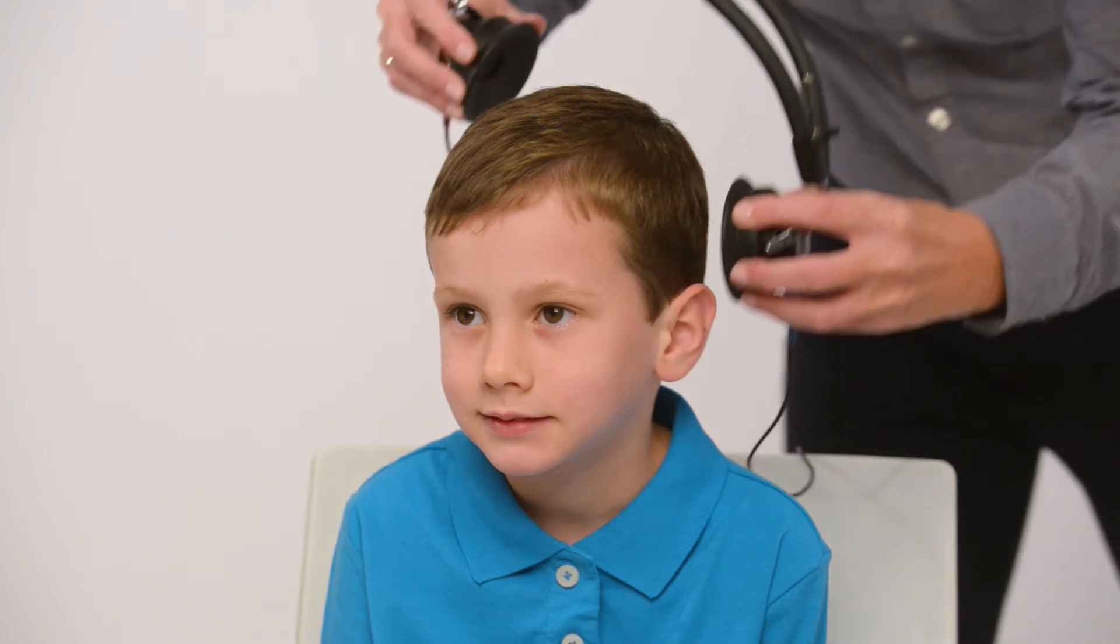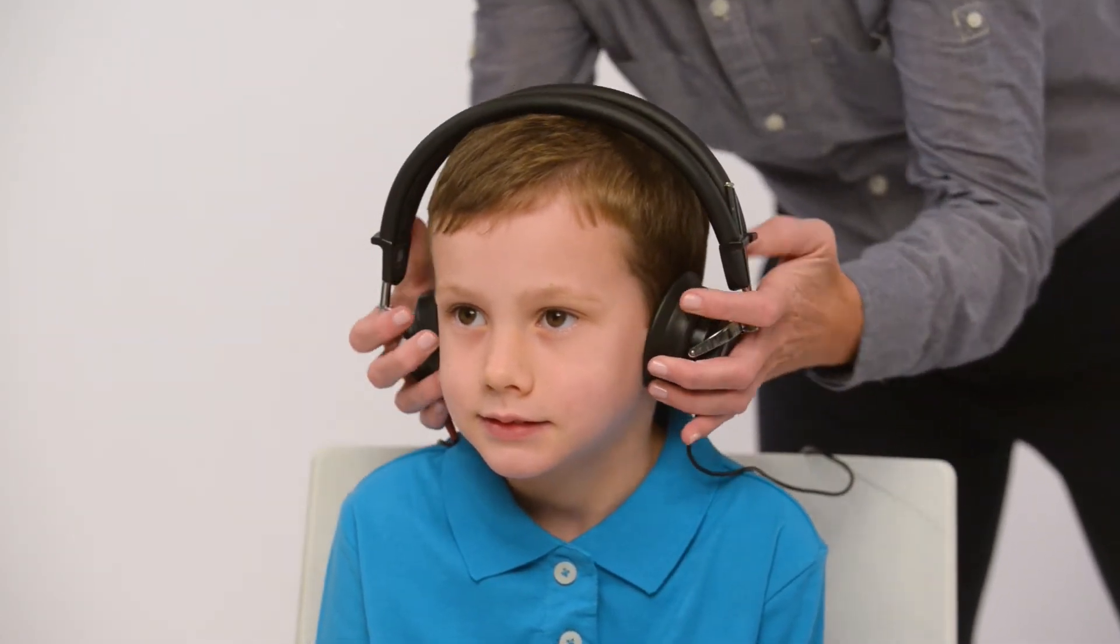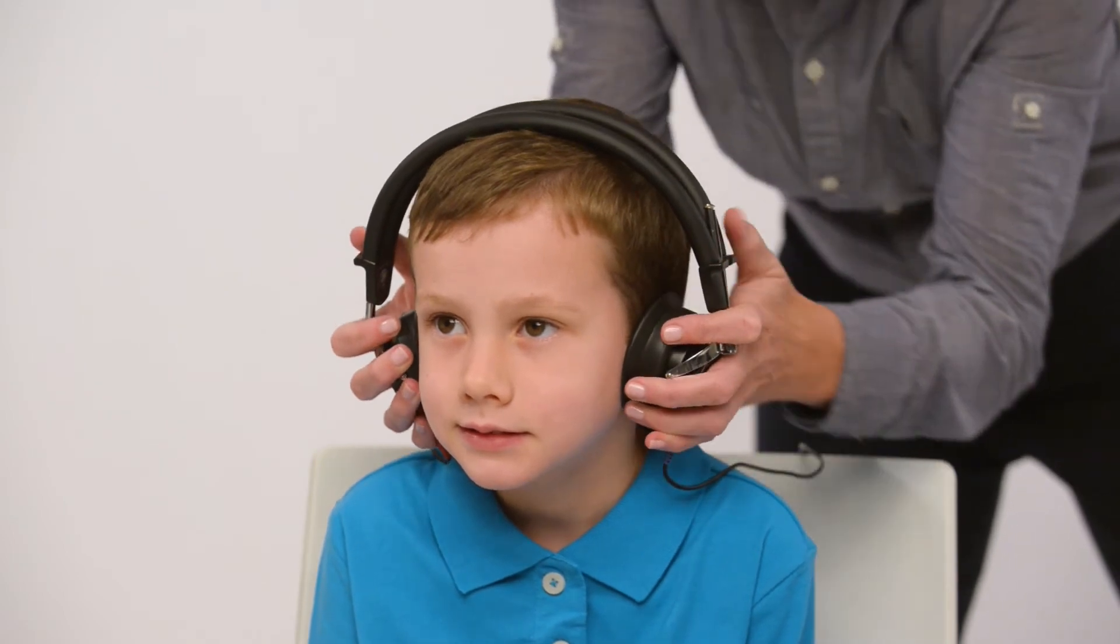Place headphones directly over the child's ear, with red phone on the right ear, blue on the left. Remove any obstructions that may interfere or be uncomfortable such as glasses. Adjust the headband so the headphones are centered over the ear canal.